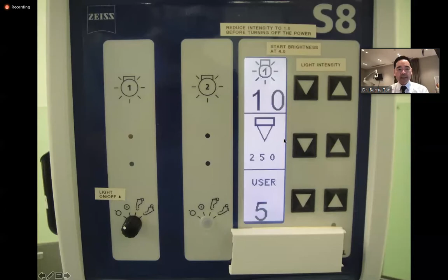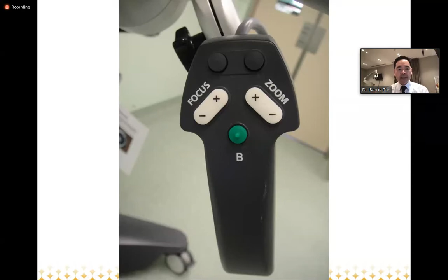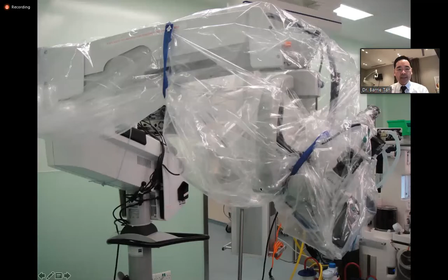Next, you need to know the functions and the controls of the operating microscope. Nowadays, there's a zoom function which magnifies and brings you very close to the operative field, but which then makes the awareness of the surrounding structures less obvious to you. The focus needs to be correctly set, and many operating microscopes also have a focusing beam that's incorporated into the viewing pattern. And this is just an example of a surgical grade operating microscope.